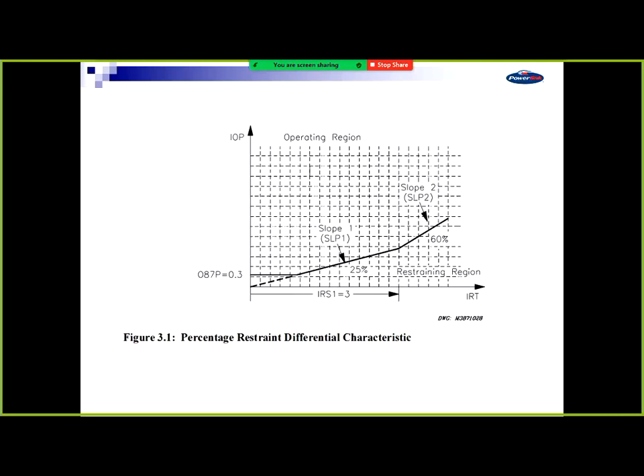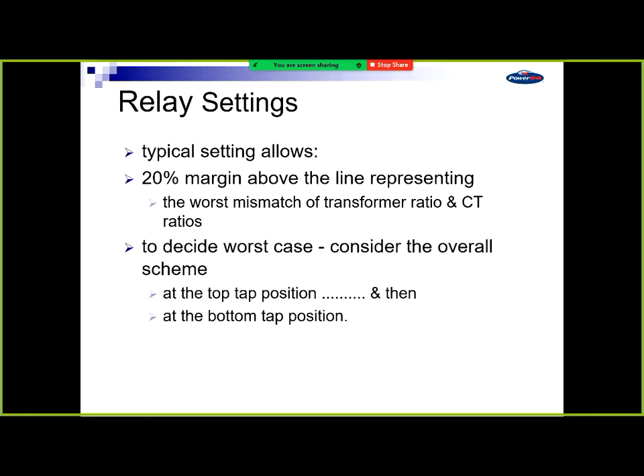Do we have something unusual in our network where we need to set that higher? So for setting one of these bias differentials, we generally go 20% above the line representing the worst mismatch of the CT ratios and the tapping. So we look at top tap, bottom tap, and see what the mismatch is with the CTs, and then put a 20% margin on that. You'll see this 20% margin put in just about everywhere with protection. It's just a safety margin that gets used, which is, again, decades old. It works.